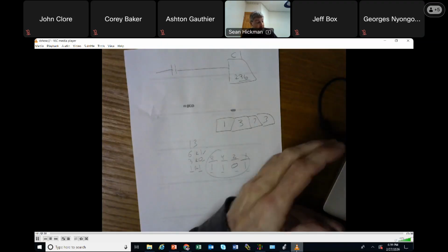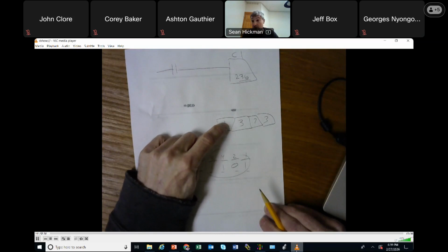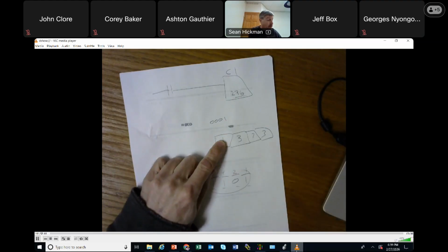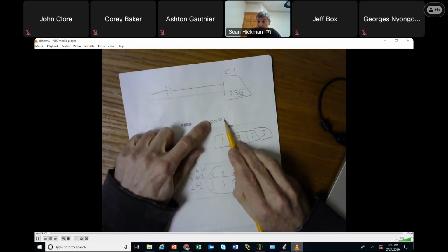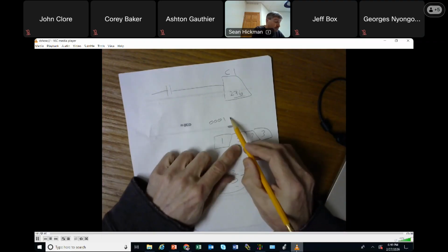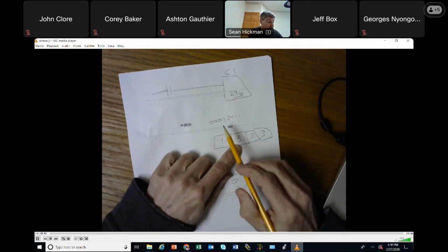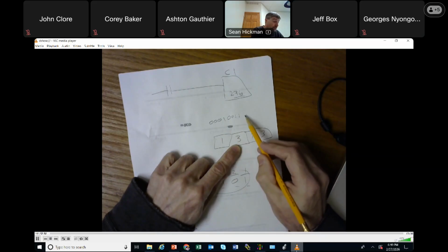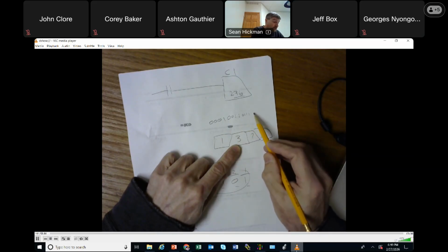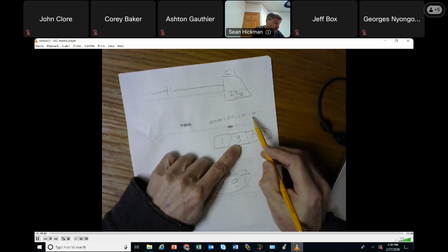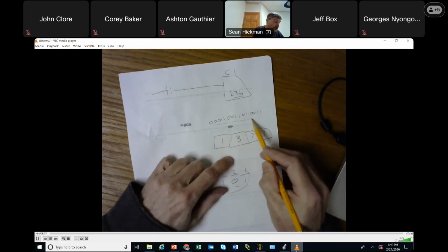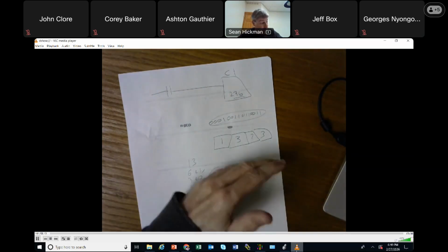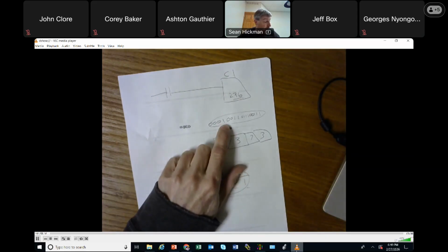It's set up so that when you have a 1 on here, you look at your input card and you've got 0, 0, 0, 1, so the first input would be on. On this one right here, it'd be 0, 0, 1, 1, so these 2 input lights would be on your input module. This one would be 0, 1, 1, 1, and this would be 0, 0, 1, 1. That is what would come in from the thumb wheel. If you set it to 1373, it reads this number in because these are the inputs that are on.